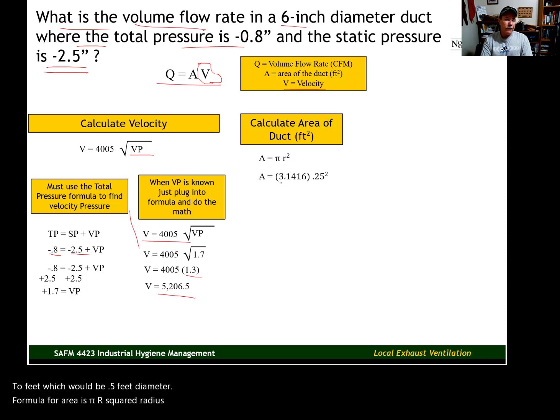Radius is half the diameter. So we take that 0.5 foot diameter, divide that by 2. We have a radius of 0.25. Then we square that. And pi is pi. Multiply pi times 0.25 squared. We end up with a cross-sectional area for this 6-inch duct of 0.196 square feet.